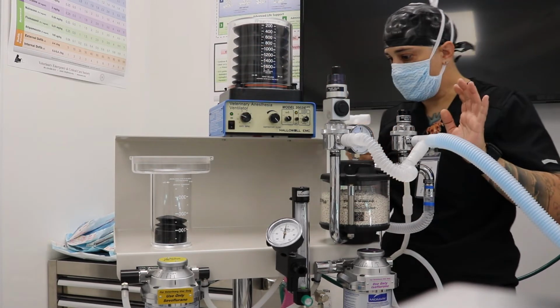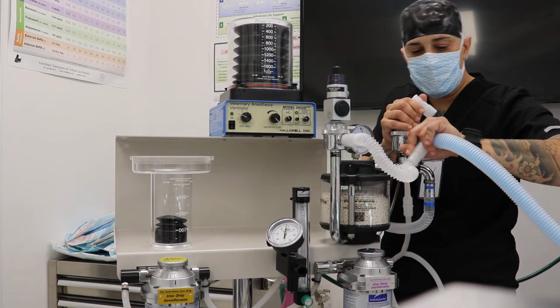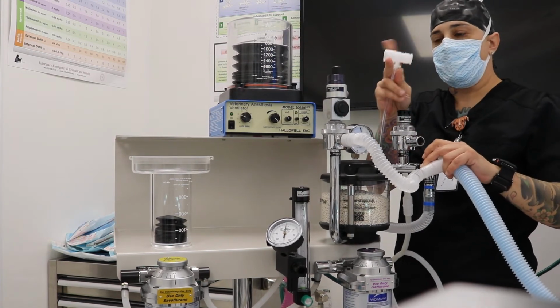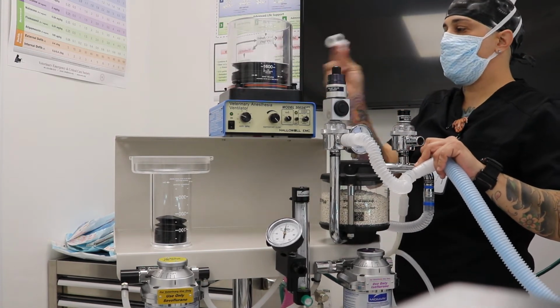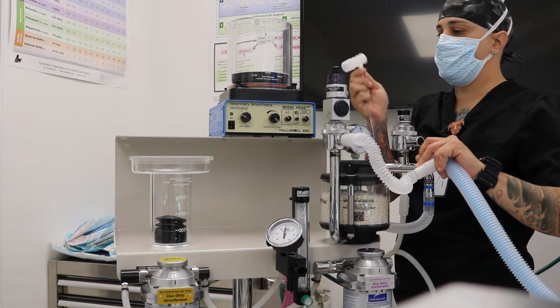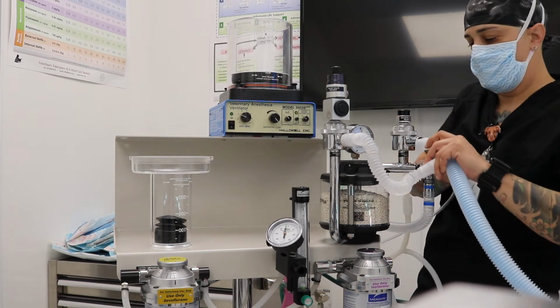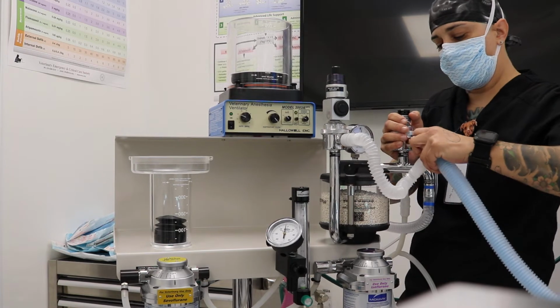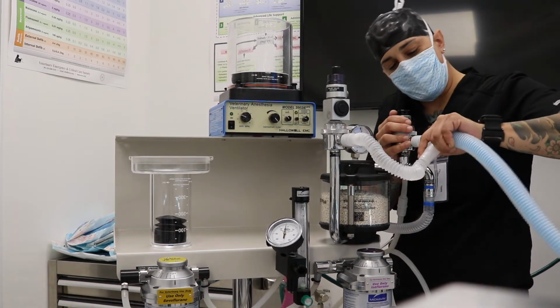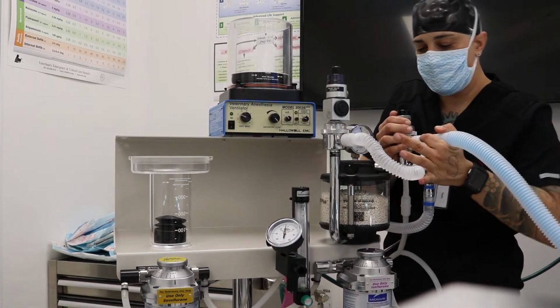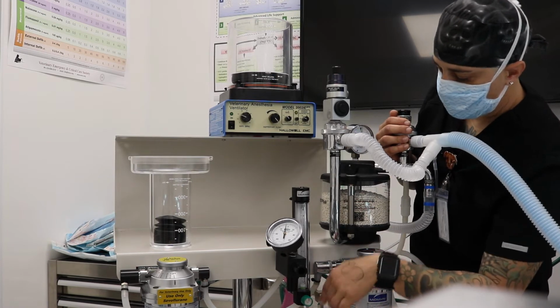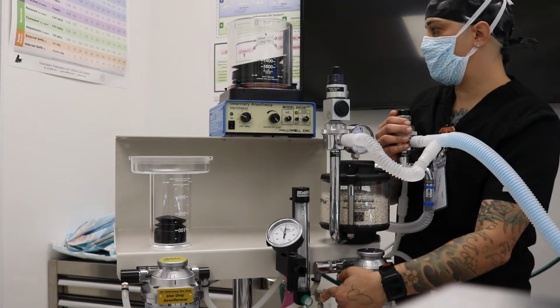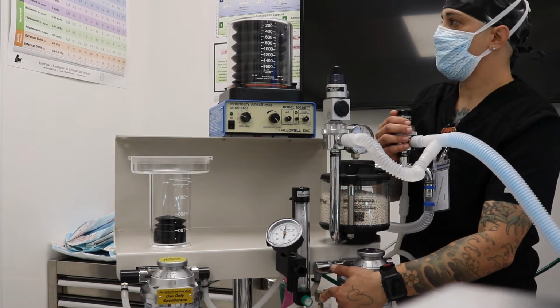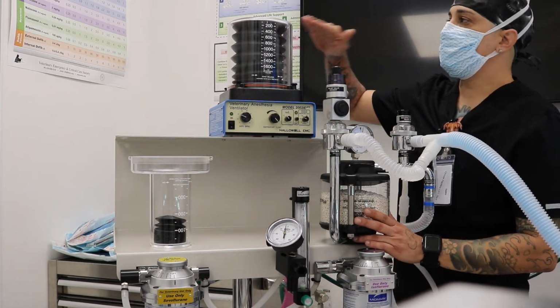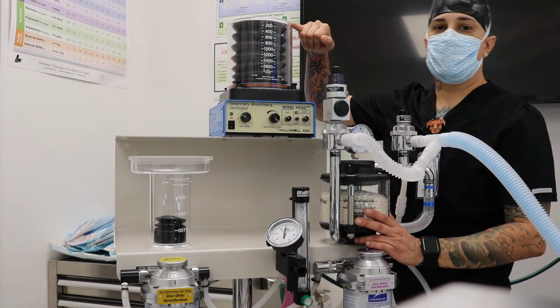To combat that sound, which is quite loud, this goes on the inspiration. This will tell this machine how much pressure to give to your patient, and on the inspiration only. So we just connect that right there, get it on nice and tight. Put your breathing circuit back on to that, just like that. Now, where's my little flush valve here? Flush the bellow back up.